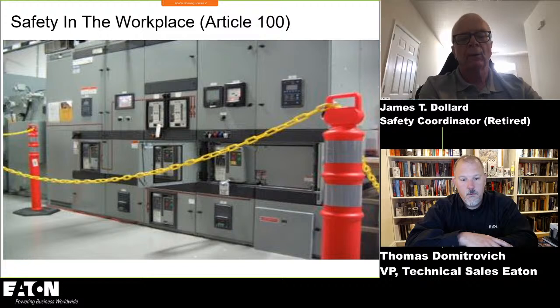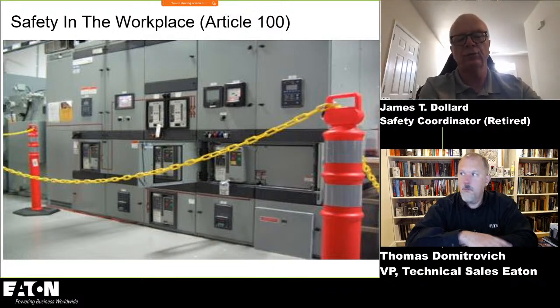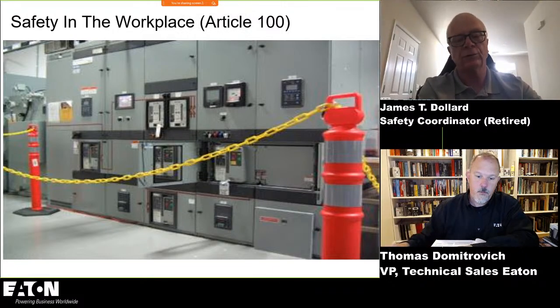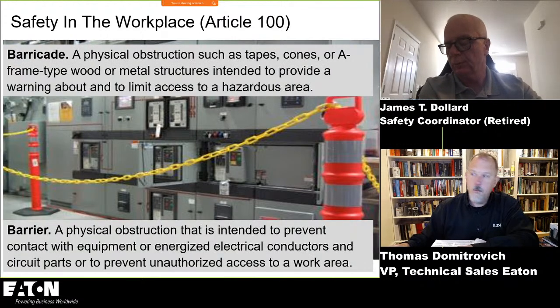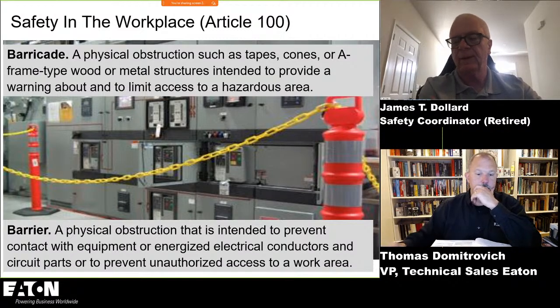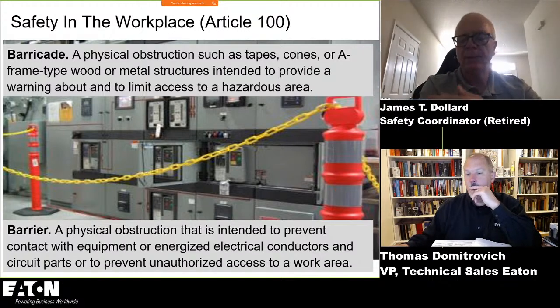Well, when you're doing an arc flash risk assessment, you're either going to be using the tables, or you have labeled equipment, which means an incident energy analysis was performed. So if we can look at the equipment, we're going to see the voltage. And it's a function of training that we're going to look at it and understand that I've got a limited approach boundary of 3'6". I've got a restricted approach boundary of 1 foot. And then on that label is going to be my arc flash boundary. If I'm using the tables, I'm going to get my arc flash boundary from the tables.